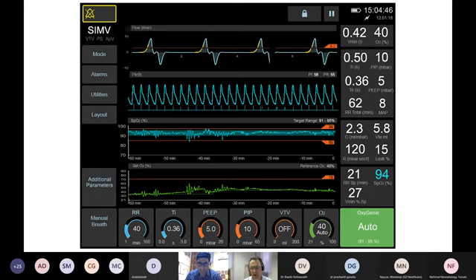Interestingly, through manual control on a ventilator, we can expect 40 or 50 adjustments to the blender in some cases per hour, which is rather difficult for a human being to keep up with, as is a changing SpO2. So automation of that process is a very interesting step forward, and of the papers that have been peer reviewed and published so far, the data demonstrates significant improvements in time in target range, and also a reduction in hyperoxia and hypoxic or severe hypoxic episodes for infants as a result of closed loop oxygen control. So that's bringing SpO2 technology integrated into ventilators, and that's pretty much where it brings us up to date these days.